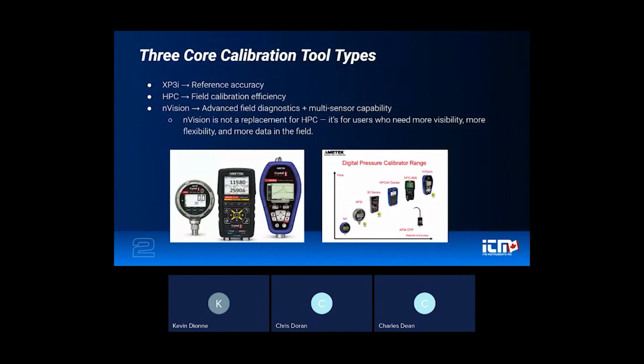Before we move on, I just wanted to go over what we've spoken about from an instrument perspective so far. So the XP3i, the first one that we spoke about, it's all about reference accuracy. It's a trusted reference gauge. It's used with the pumps and the calibration systems that I spoke about as well, when accuracy is your primary requirement. The HPC focuses on field calibration efficiency. It combines pressure generation and measurement into one device. It's ideal for fast on-site calibration and verification.